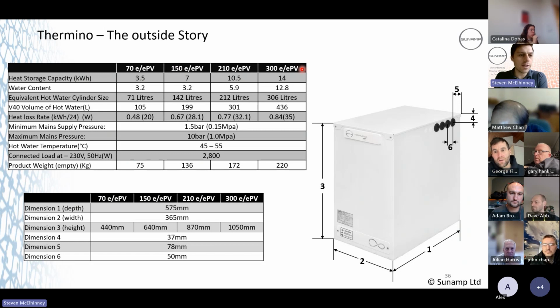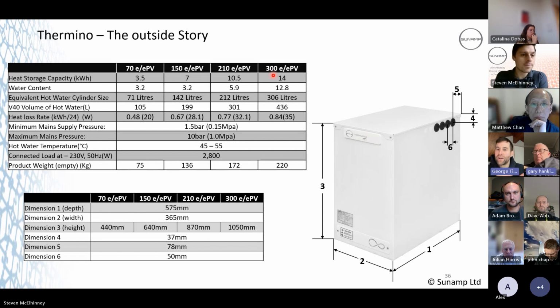Yeah, so if you've got that TMV set at 55, George, your capacity in litres will be less. But if you've got your TMV set to about 45, 48 degrees on the outlet, you will achieve that 300 litre mark. Cool. I know 40 is a standard that cylinder manufacturers use to give. It's like a heat pump at 7 and 35, isn't it? It's the standard kind of thing. Okay. I mean, if I was to say to my wife, you need to have a shower at 40 degrees, she would just look at me with that funny look that they give you. So a lot of shower mixers ask for an approach temperature of 55 in order to work the cartridges properly. So it's a bit low sometimes.